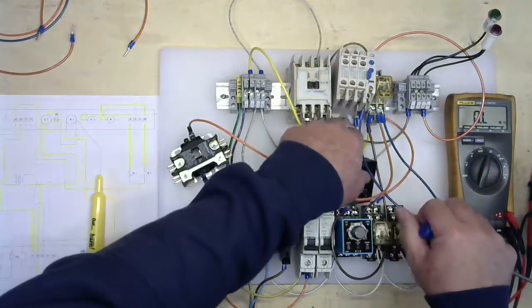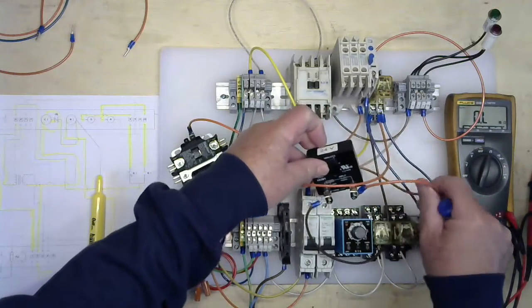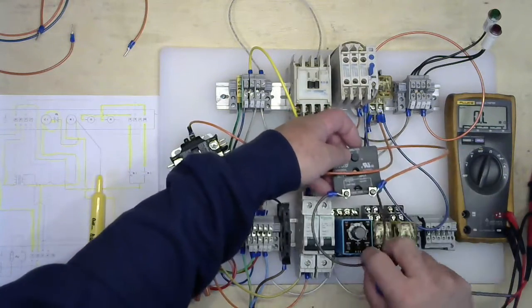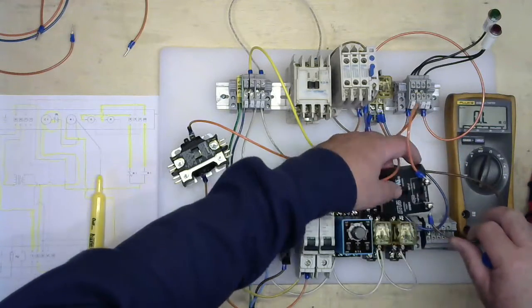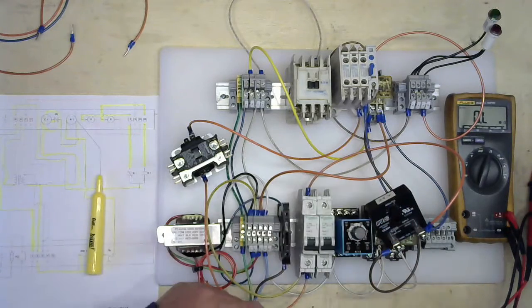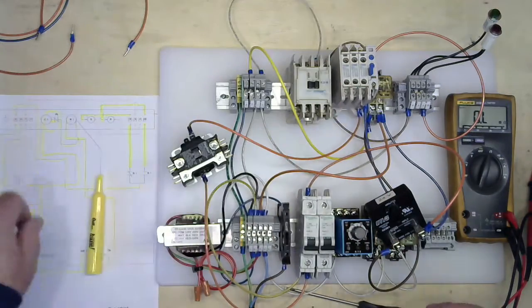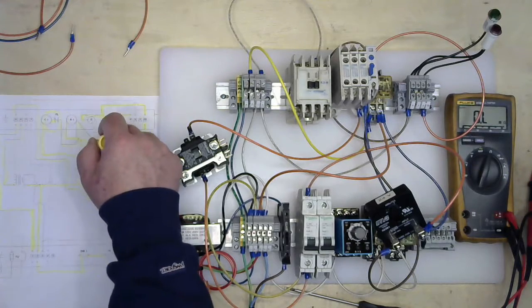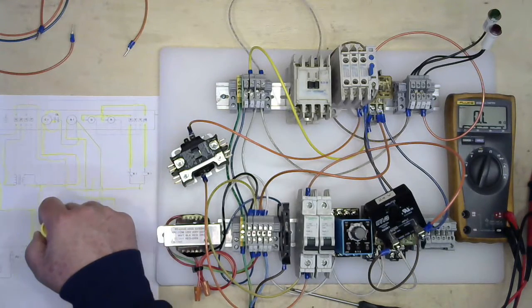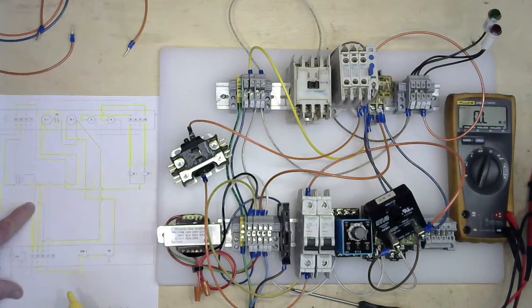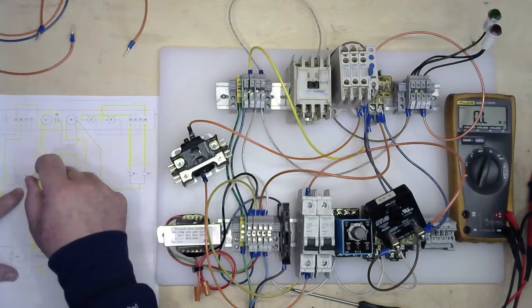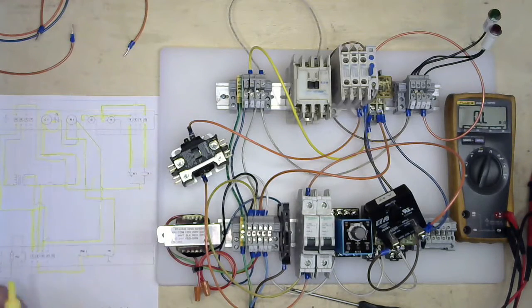Let me move this around just a little bit. As you can see, after a while, the amount of wiring gets a little bit cumbersome to test everything out. So now I have my overload block. I have relay 1 coming down, terminal 3, and then we know our transformer is already connected to terminal 3. So now as you look at all this, you see highlighters over every part.